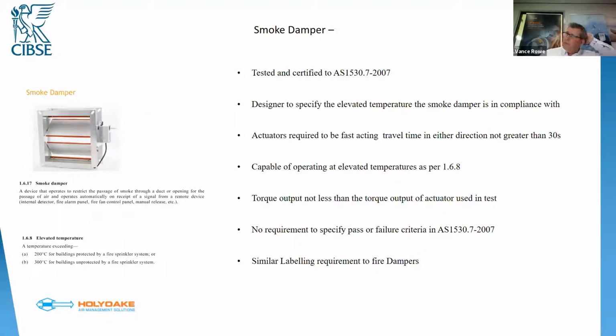Smoke dampers, these have caused quite a lot of contention actually since about 2015. They're required to be tested and certified to AS 1530.7, 2007. And it's absolutely critical that people understand that. A lot of the fire/smoke dampers that are in the marketplace today were actually only tested as a fire damper. So they were tested to AS 1530.4, often the 1990 version of that, because at that time there was not a separate definition for a smoke damper. And interestingly, the grandfather clause in the NCC does not cover smoke dampers. So the smoke dampers that are going into buildings right now really do need to be tested and certified to AS 1530.7, 2007. And it's critical that people understand that definition.